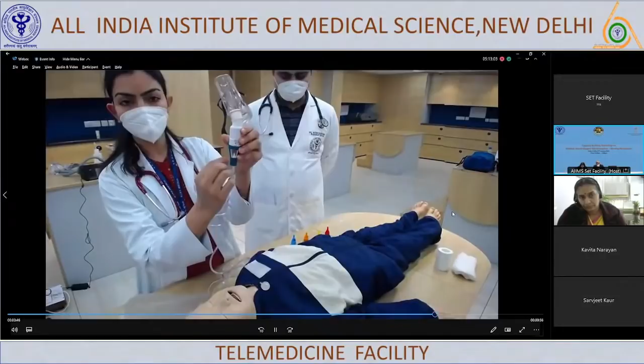And this is a variable adjustable device. There is a nozzle here which is a very small opening. It will generate a high negative pressure which will lead to entrainment of ambient air, and the patient is breathing in through these holes. The flows provided by this device are very high. That is why it is classified as a high flow device.